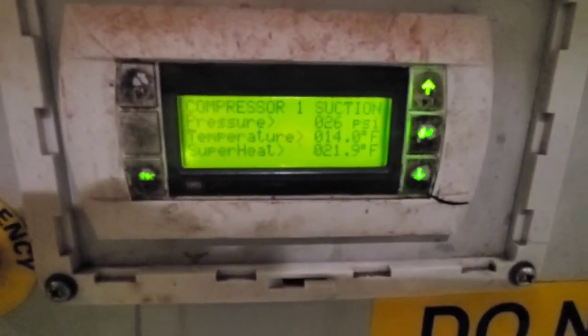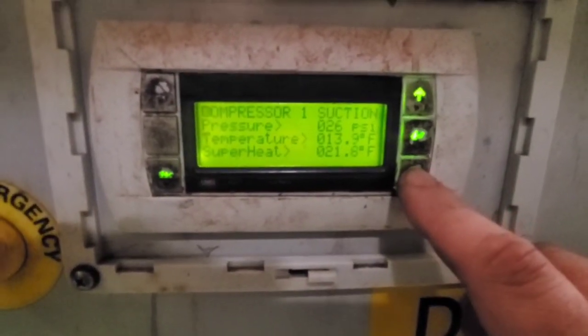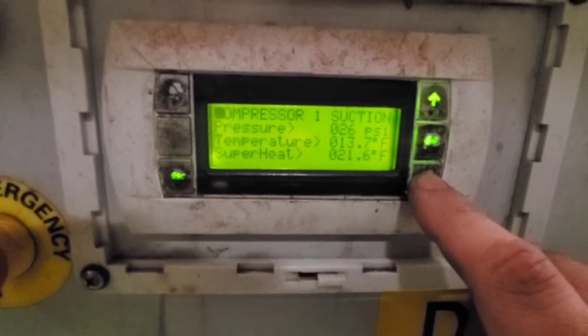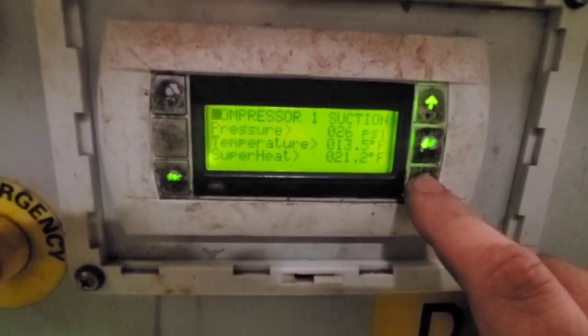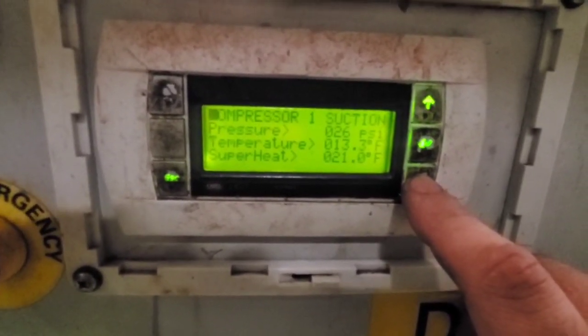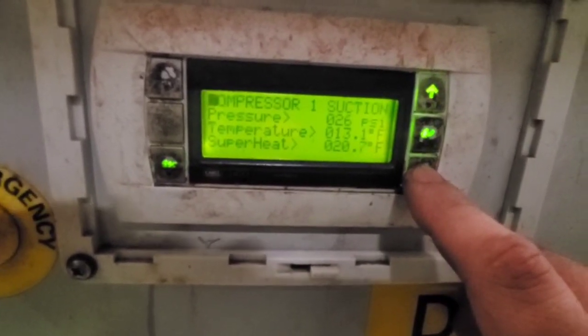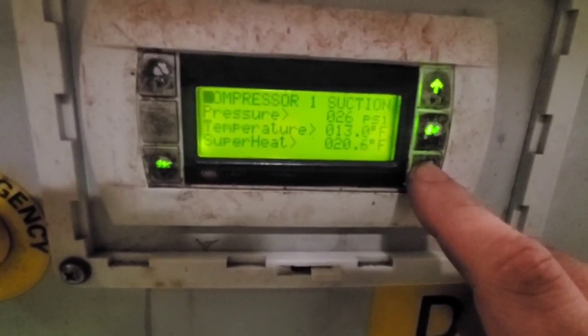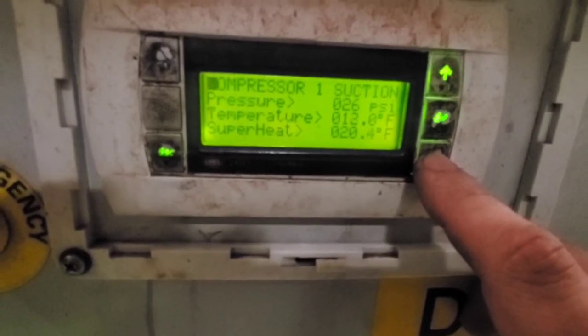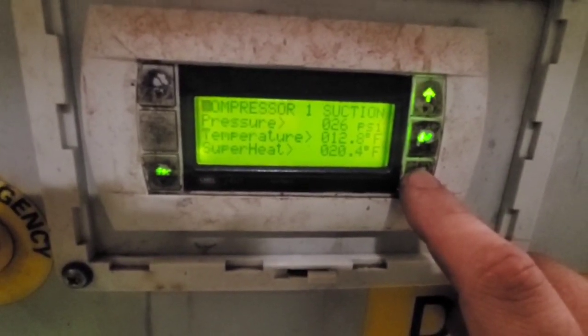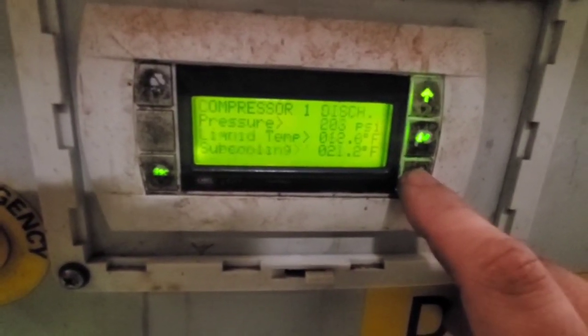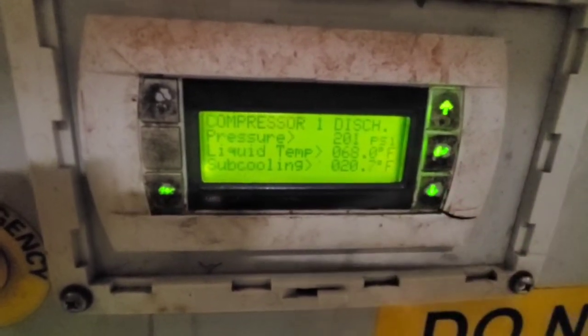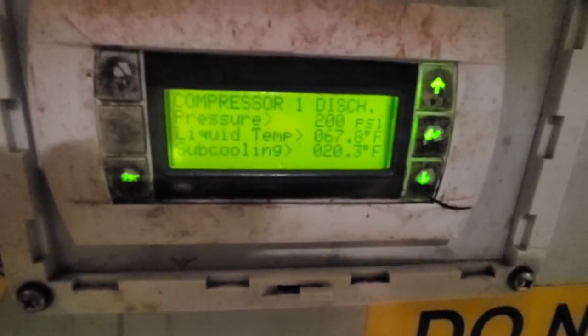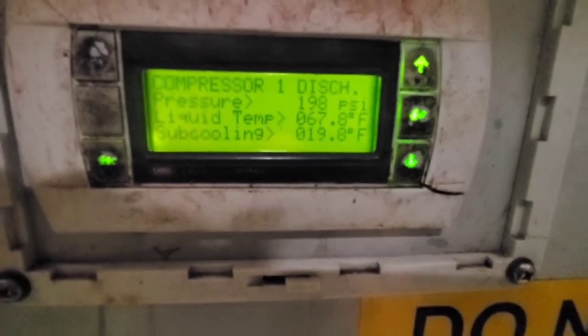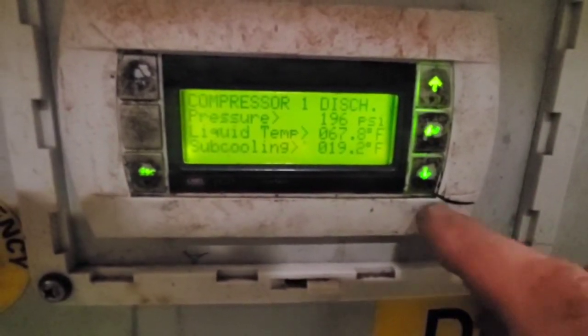And we're also going to observe some of the pressures and temperatures of circuit 1 before we leave it running and shut down circuit 2. If there's any issues with circuit 1, we're not going to switch it over to circuit 1 until we fix those issues, because this chiller has to remain running on at least one circuit. So our compressor 1 suction and discharge numbers are normal. We've got 20 degrees of subcooling. It's going to float around there.